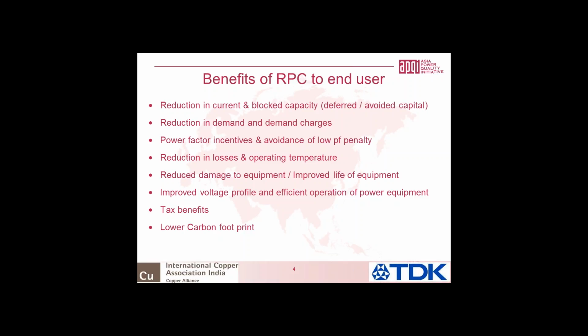When you have a unity power factor, you have less reactive power demand, and your demand charges do come down, especially in a country like India, where it's a 2-part tariff. You have an energy tariff and you have a demand tariff. You can save a lot on your demand charges. In some states and some countries, of course, you have special incentives and penalties for low power factor. So if you improve the power factor, either you can avoid a low power factor penalty or you can get an incentive for maintaining a higher power factor.